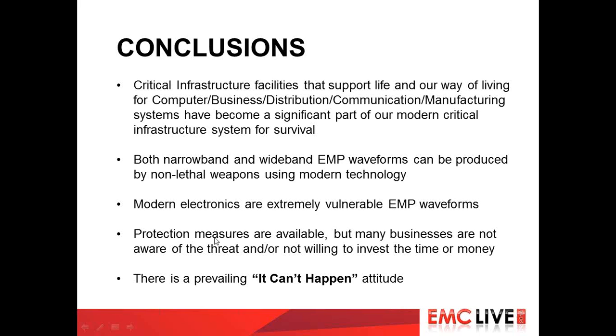All modern electronics are extremely vulnerable to EMP because of the nature of electronics getting more compact and smaller every day, operating at smaller voltages. And a 50,000 volt per meter signal with a non-classified 10 nanosecond rise time and a 15 nanosecond fall would really destroy any electronics that are in its path. The protection measures are available, and we've gone over some of them here. But many businesses that support critical infrastructure are not aware of the threat. Over the past few years, I've seen an increasing interest in the threat of electromagnetics, and more so IEMI than HEMP.